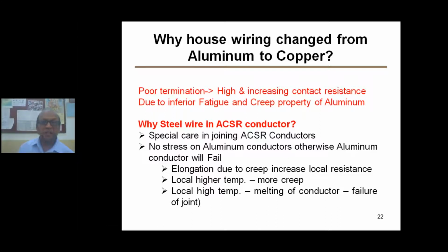When you tighten aluminum wiring, with time, maybe one month, maybe six days, maybe six months, it gets loosened. Loosening means it undergoes permanent deformation because of the poor creep behavior. Then contact resistance increases and there is burning. That is why houses have changed wiring from aluminum to copper, but we have never thought of changing aluminum to copper in transformers, where transformer wiring is all the time subjected to many stresses and forces.